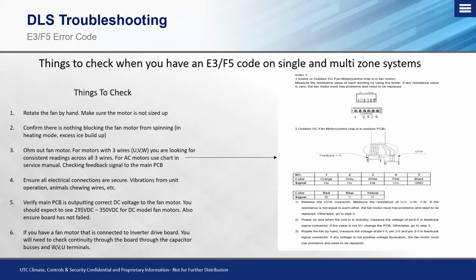The second thing that we want to check is to confirm that there is nothing blocking the fan motor from spinning. If there's anything caught up in there, some debris, or more importantly, in the heating side of things, if we start having defrosting issues where the coil is not defrosting properly and we're getting excessive ice buildup, that can certainly make its way into the path of that condensing fan motor and of course block it. Then you'll end up with an E3 or an F5 code, depending on where you're looking on that system, pertaining to a fan motor issue because it's not able to spin properly.